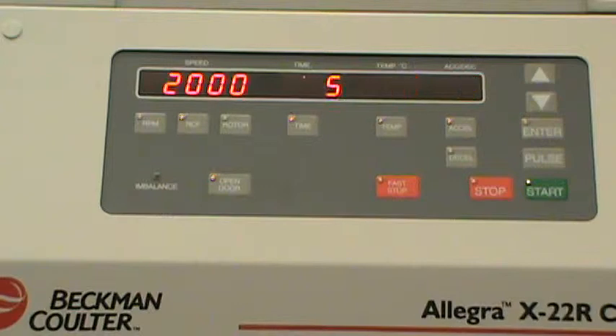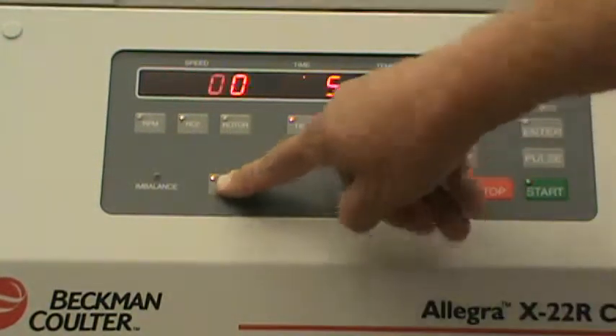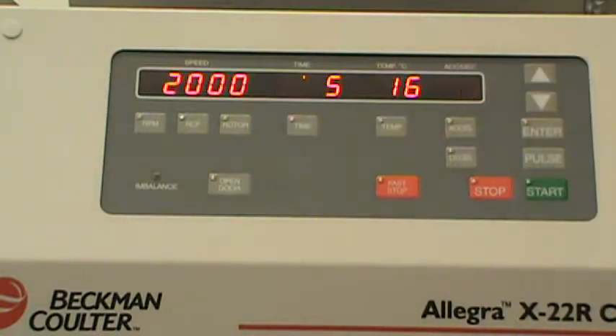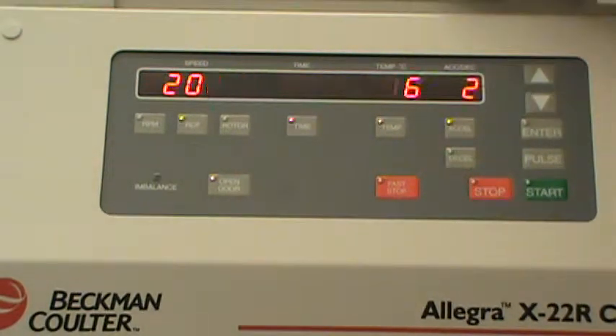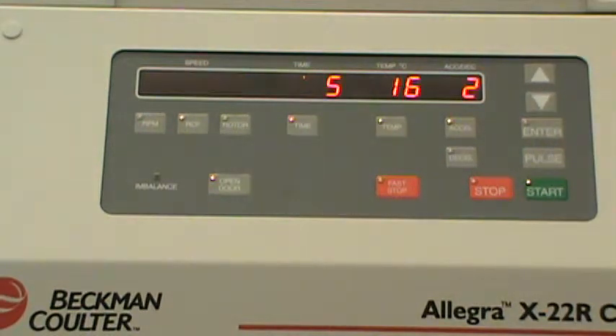Now, one thing to remember, because this is a refrigerated centrifuge, if you open the door to the centrifuge, you'll let all the cold air out, and you will start to have condensation build up in the machine. Therefore, we want to keep this machine closed as much as possible. You do have to open it in order to get material in and out of the centrifuge, but please try to keep the time that the door is open to a minimum.